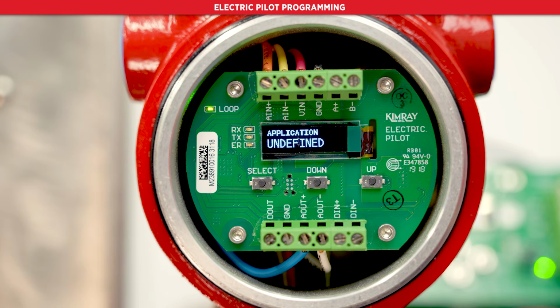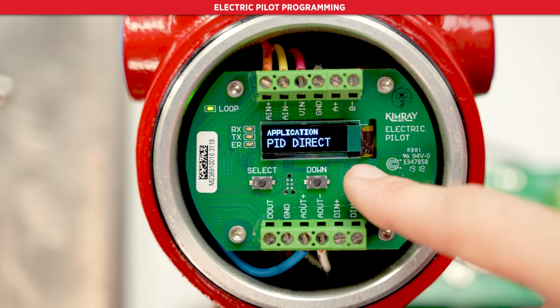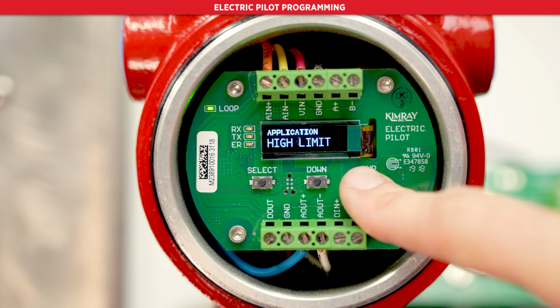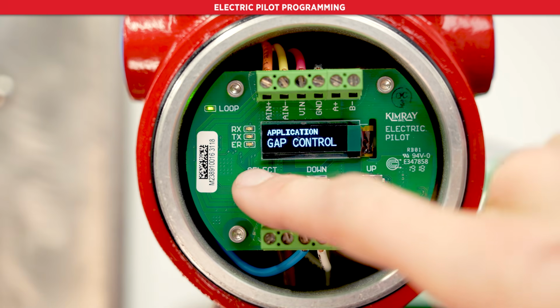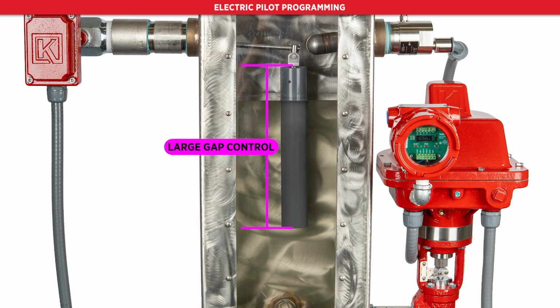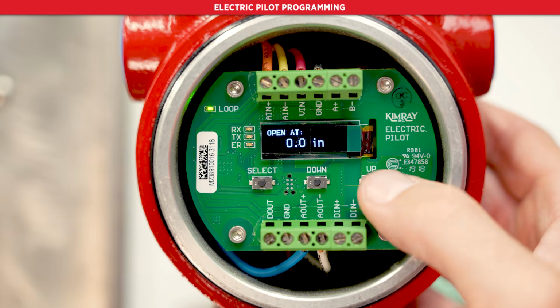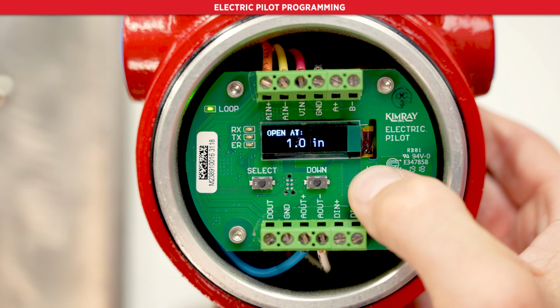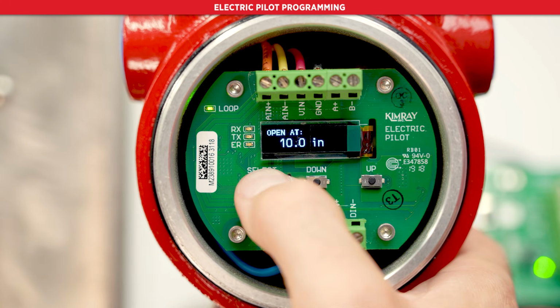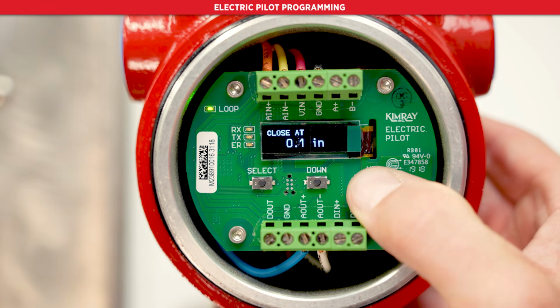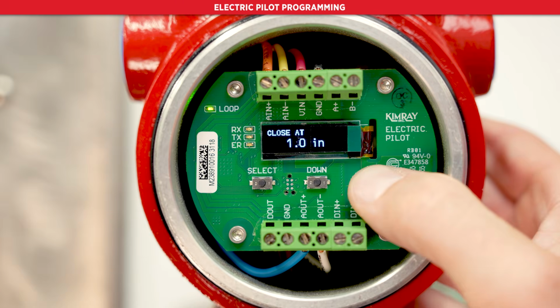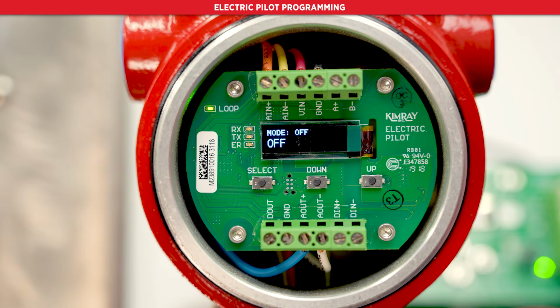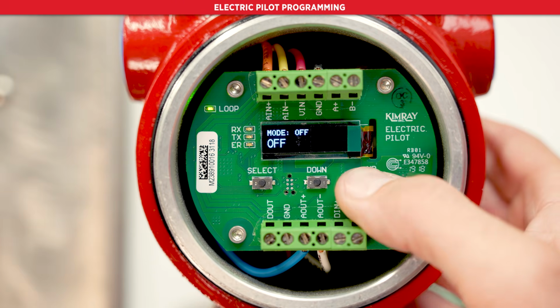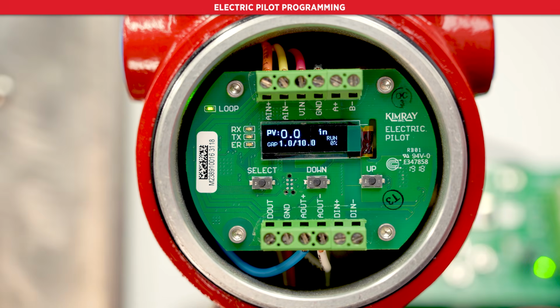Now we will define the application. For this setup, we want gap control. This is the most frequently used application because it can control a gap as wide as your displacer or down to a very small gap to accommodate your control needs. We will set the high side of our gap control to 10 inches. This could be anything within the min and max of the displacer. The low side of the gap control tells the valve when to close. We'll set this to 1 inch, then press select. Now use the up or down buttons to get to run mode, then press select.